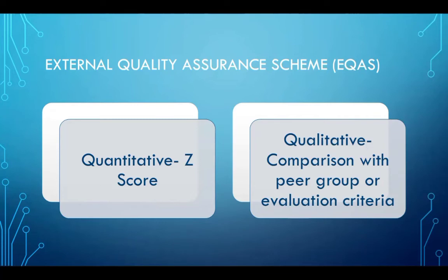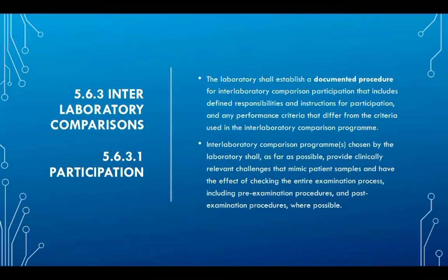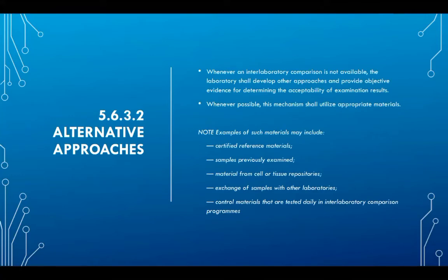This we have to understand. And participation in EQAS is a requirement of ISO 15189. The laboratory shall have a documented procedure. In this, you are defining responsibilities, who will run this sample, and participation in the EQAS is mandatory if some national program is available. If some national program is not available, you can have alternate approaches, like exchanging samples with another laboratory and defining your acceptability criteria.